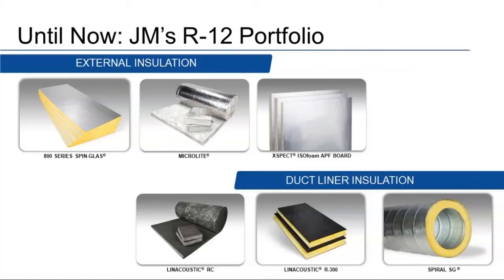There's 800 Series Spin-Glas, which would provide an R12 at a 3-pound density and 3-inch thickness. There's also our Microlite duct wrap, which we offer in a 4.4-inch thickness to meet R12. And we also have Xspect, which is a Polyiso board for external duct applications, and that's going to give you an R12 at only a 2-inch thickness.